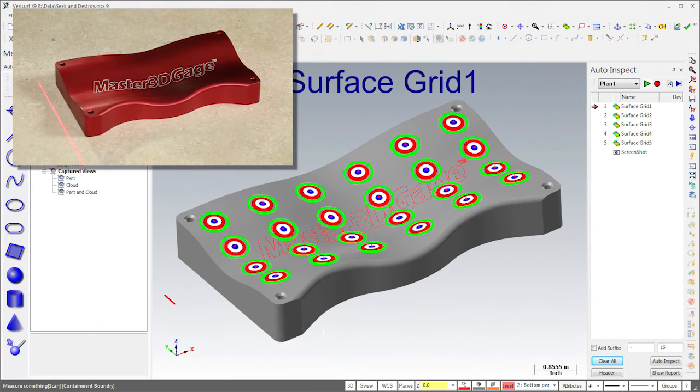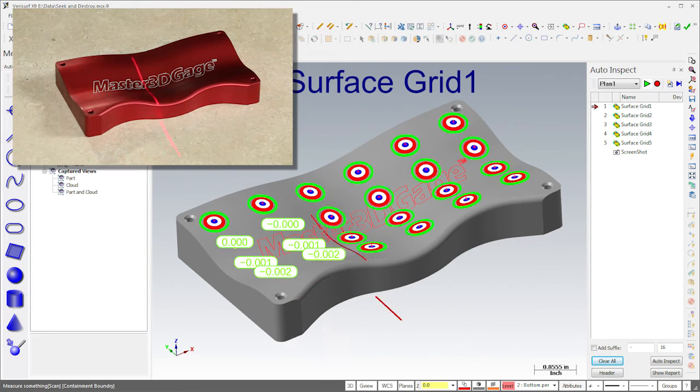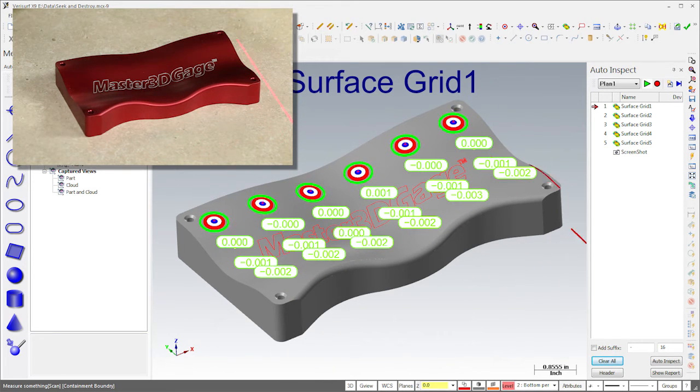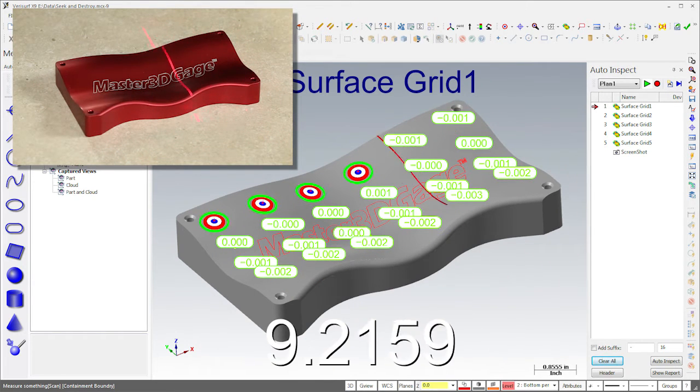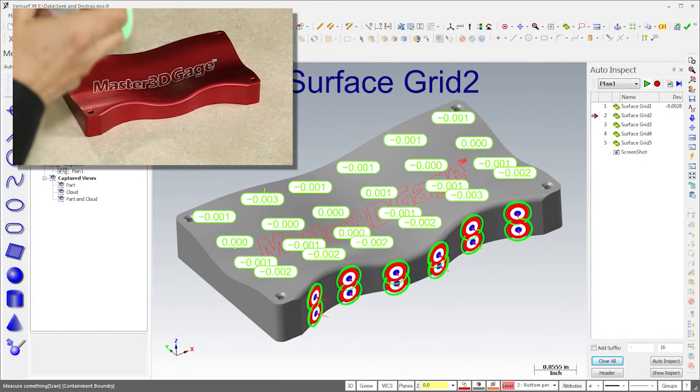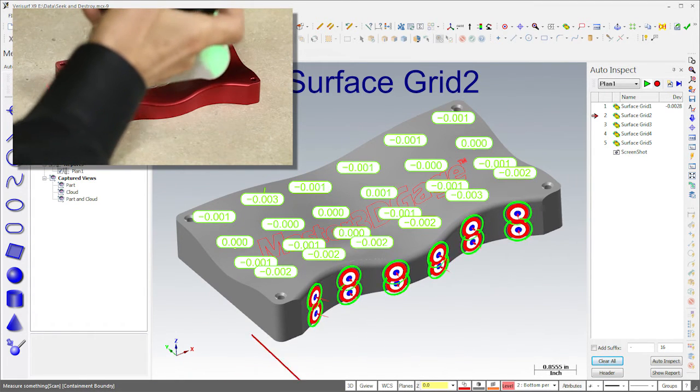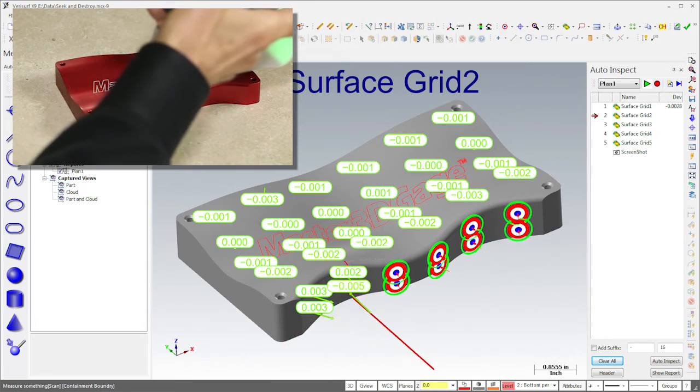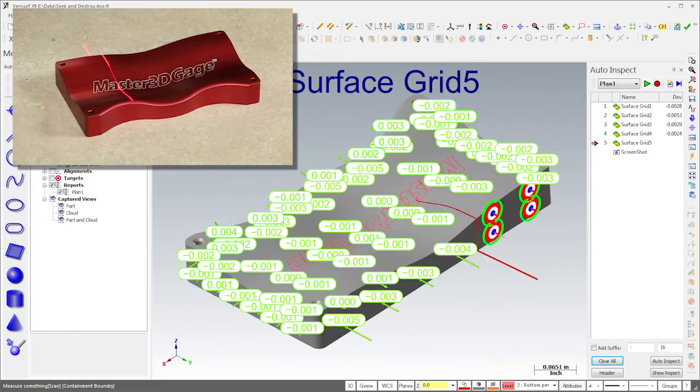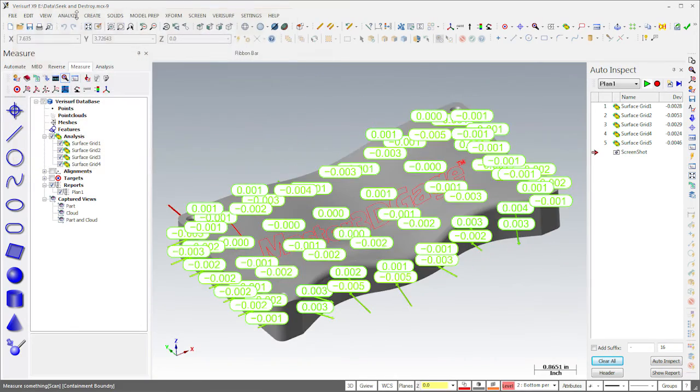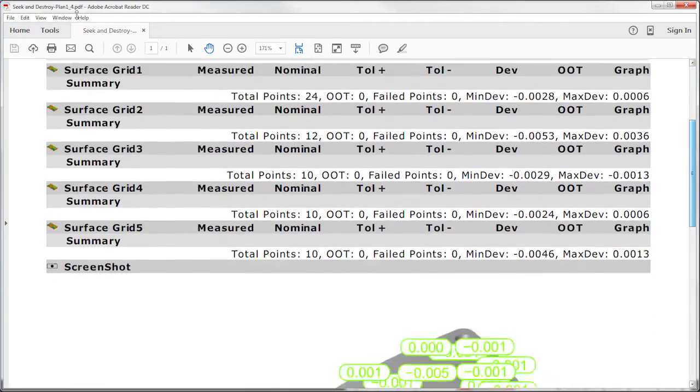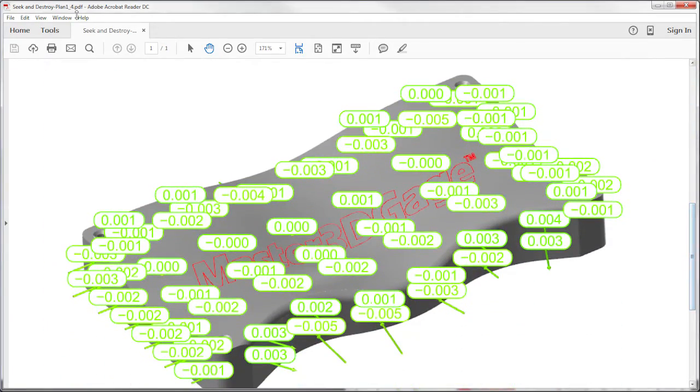To measure the targets, I simply sweep the laser across the part. Verisurf averages the values in each target zone and displays the deviation. I'll complete the inspection by measuring the targets as each grid is highlighted. Notice that the plan automatically displays the best view for each grid. After the last grid is measured, Verisurf displays a summary of each surface along with a screenshot.